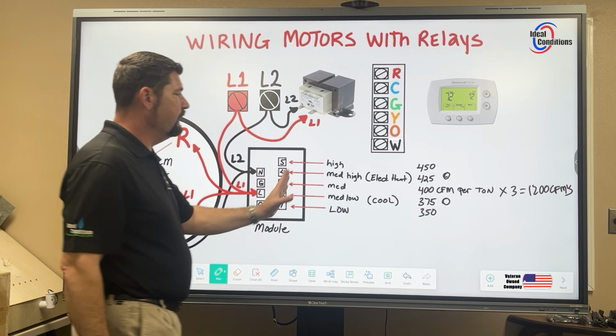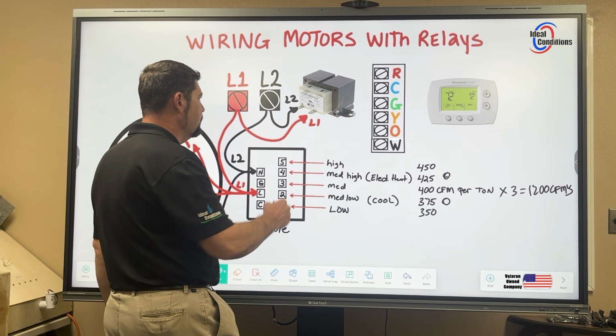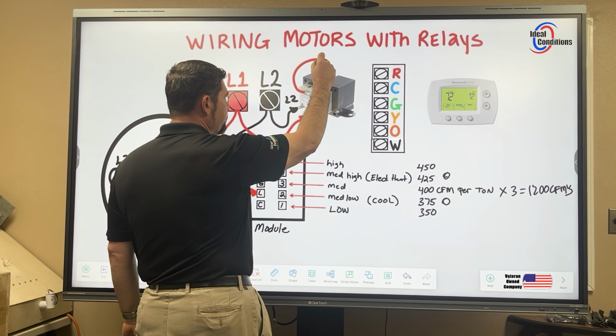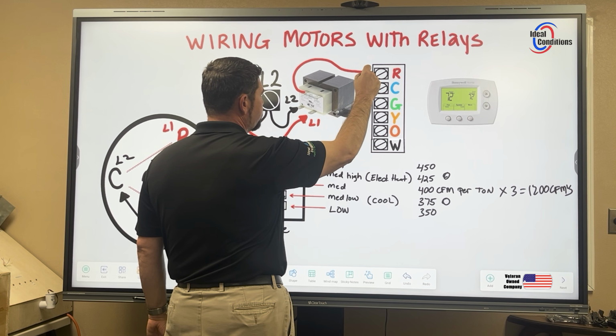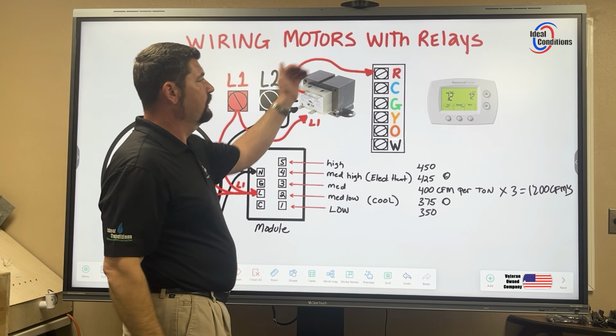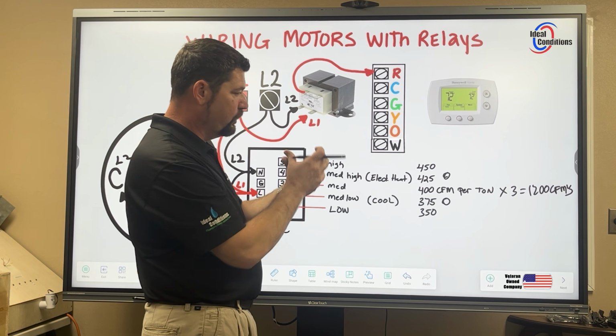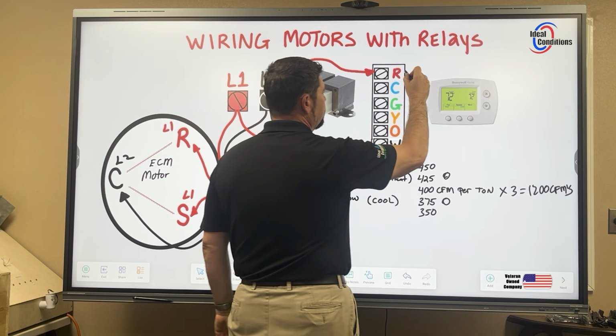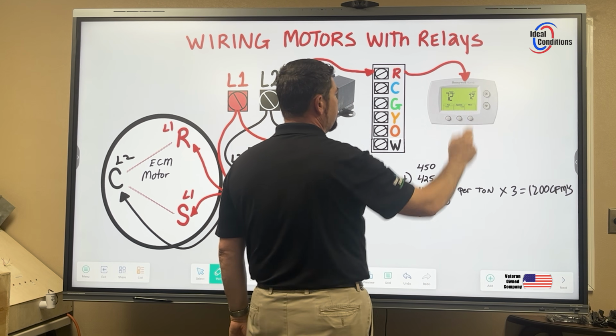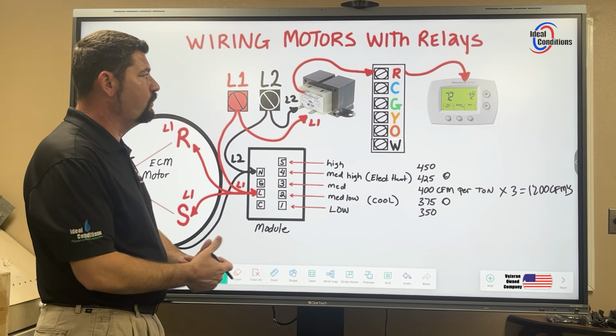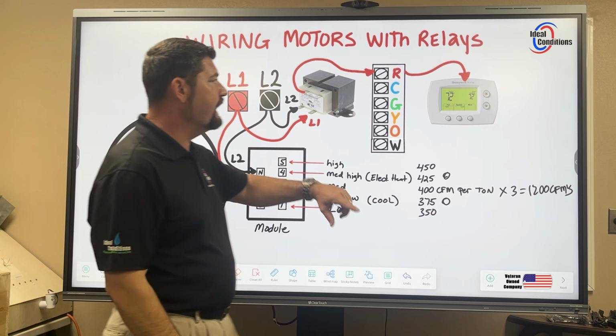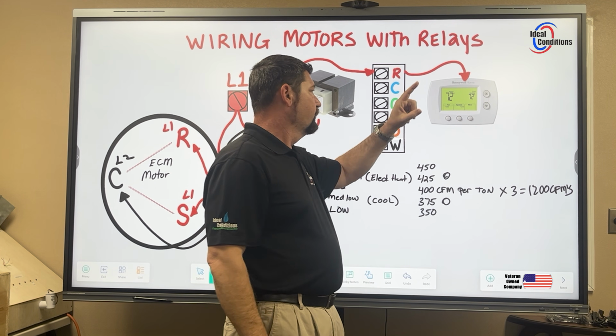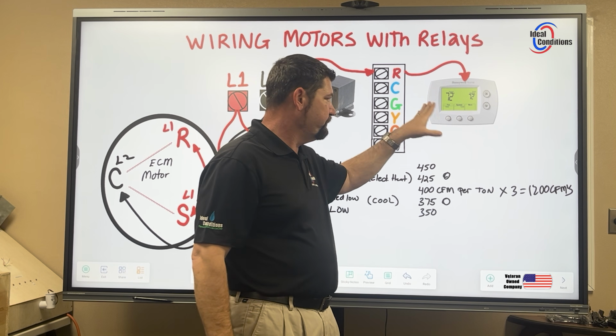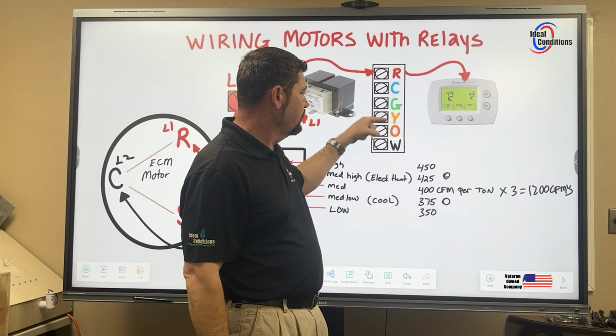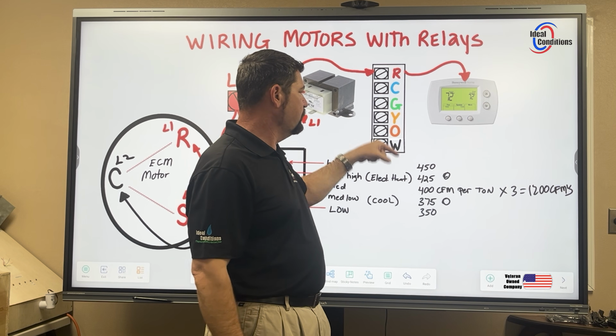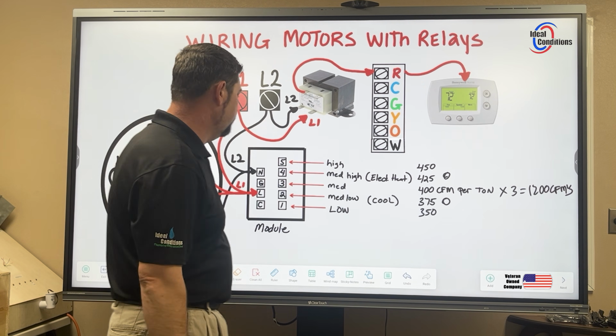So this is going to be relayed from the thermostat. So we're going to take 24 volts. Typically you would go through a fuse, maybe a transformer, a float switch, and then get over here to your low voltage terminal board. And then out of that, through your 18 gauge 8 thermostat wire, going over to your thermostat, that'll wire to the base plate, and that face plate will relay the power from here back through the face plate, back into the base plate, and correspond any terminal that it needs to relay 24 volts based on the programming of that interface on that thermostat.